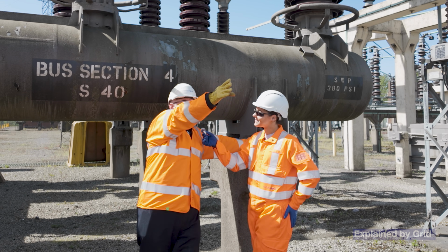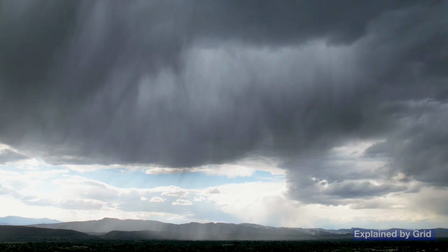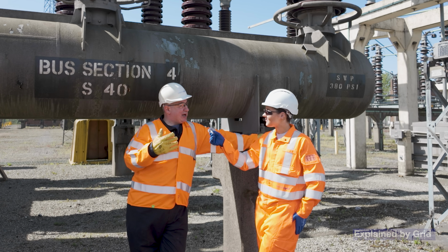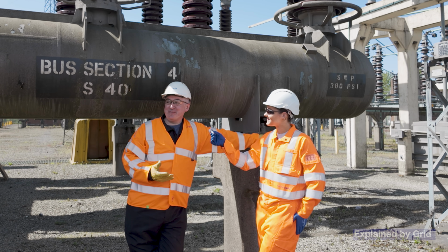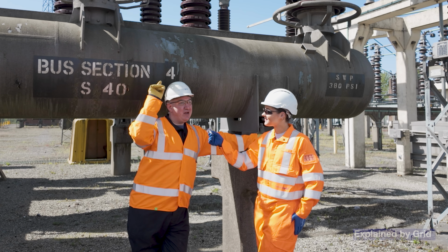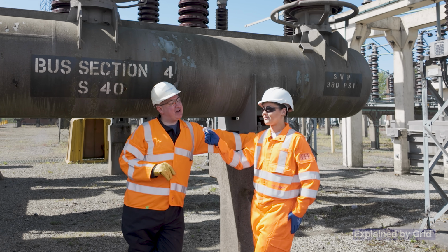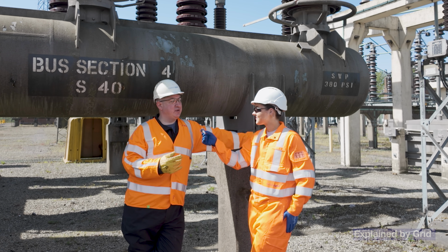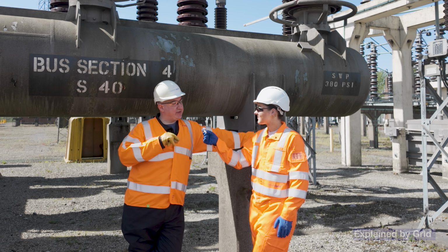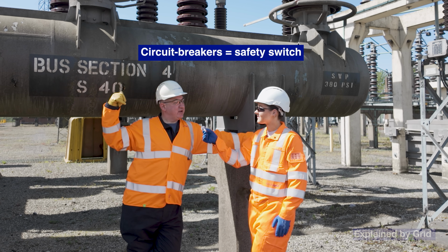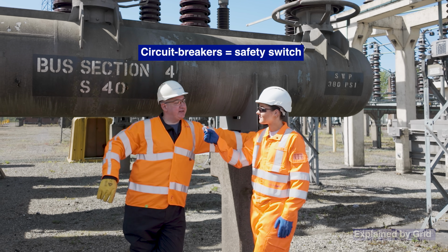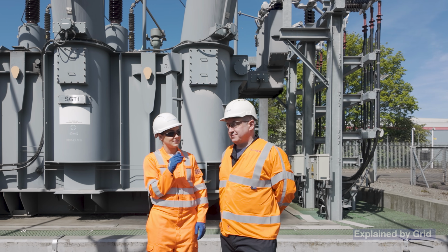So we looked at the overhead line earlier. If that was struck by lightning, which does happen in the British climate, a thunderstorm puts 500,000 volts on top of our overhead line, and a lot of current flows. We have sensitive equipment that detects that and operates circuit breakers to clear the fault and make sure the lights stay on.